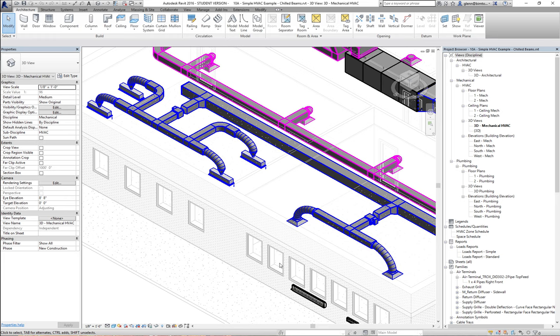And this is probably the most similar to what we actually have in the Y2E2 building above us right now. There's some sort of variable air volume unit that's controlling the amount of air. That air is flowing over the heating or cooling, and that's what provides the final heating or cooling in this room. So each of these VAVs has a thermostat that controls the amount of air, and also the amount of heating or cooling being applied to that air. That's how you get very fine control of all the rooms, as opposed to one thermostat or one air control and temperature for the entire building. By doing that, you get a lot more efficient in terms of what's happening there.